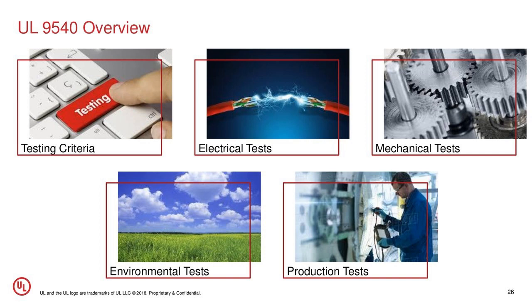But we do have a set of tests to look at the overall assembly, including electrical tests, such as an operating temperature test to make sure everything operating under load and maximum loading conditions is within the temperature range. We have insulation tests such as dielectric and insulation resistance, a surge test, impulse test, check of the grounding system, et cetera.